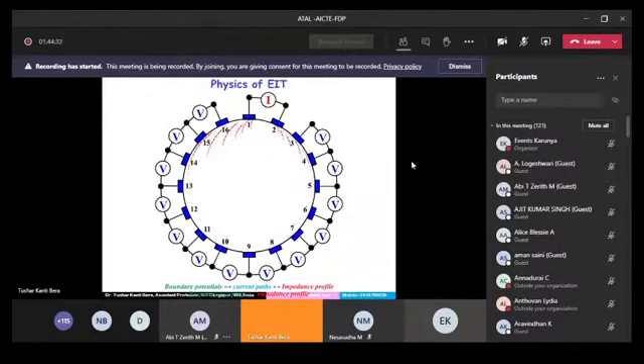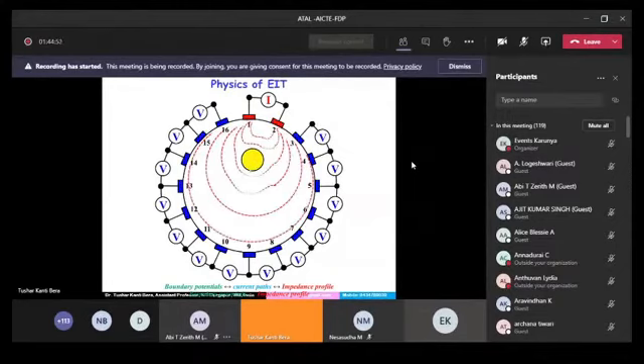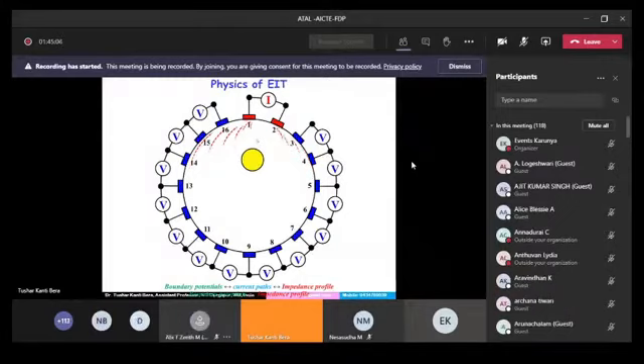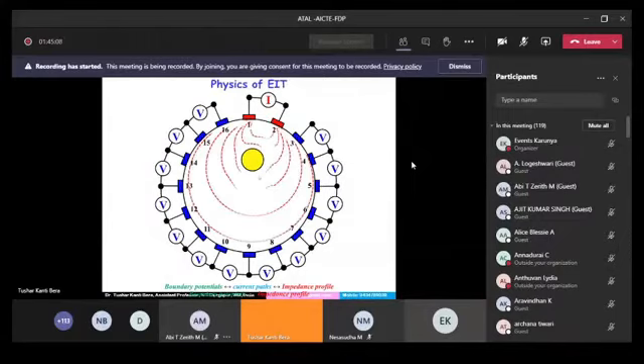How is it giving the images, how are we getting the information from the boundary measurement? If we have a homogeneous domain, then the current paths for this type of current injection will be shown by this animation. Now if we have some object, then the current paths will be distorted. If this object has higher resistivity, the current will not tend to go through it, it will try to avoid it, and the current flux will be distorted, and due to that current flux profile, there will be a change in the voltage profile. So automatically we will have the information about this at the boundary measurement.